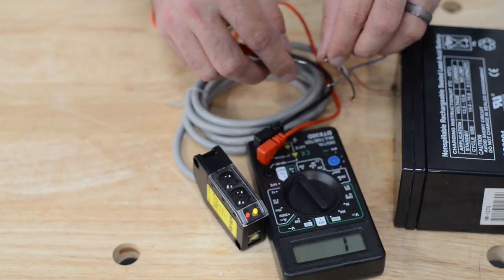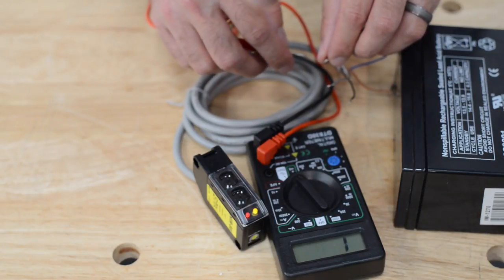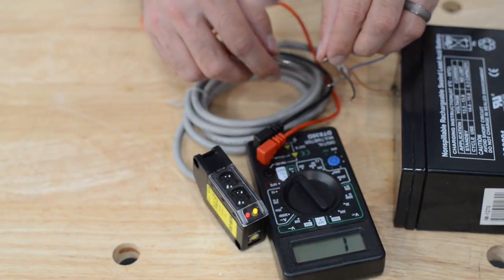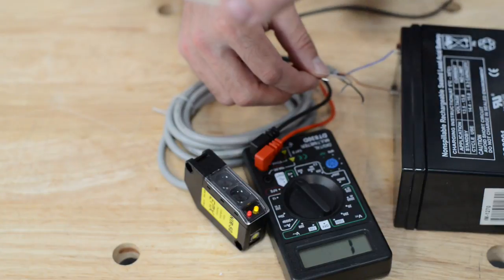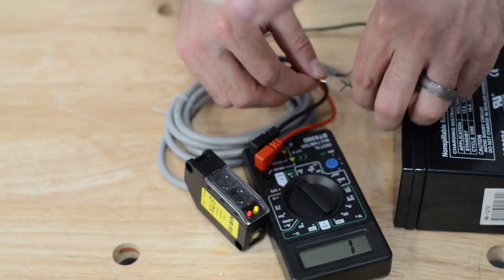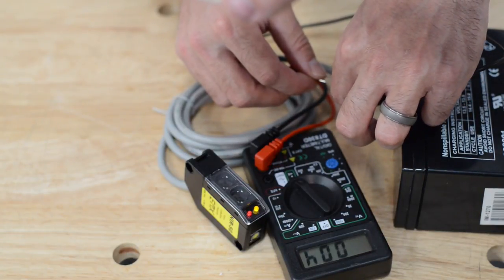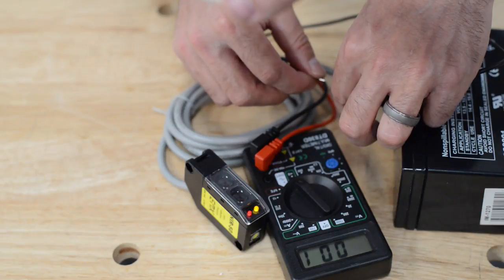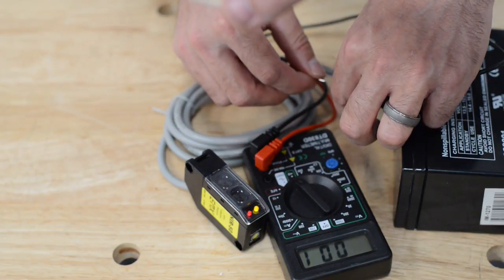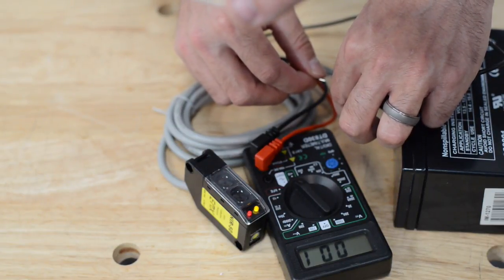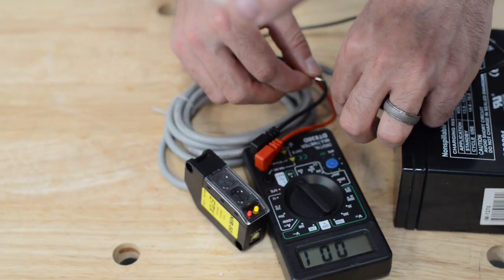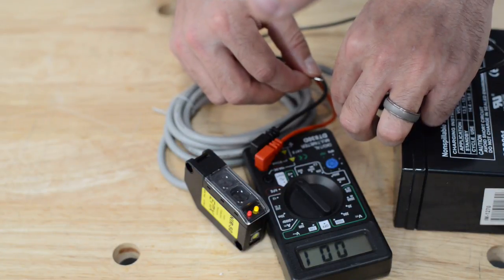So one of these two wires is common and one of these two wires is normally open. Leaving one on the white, I'm going to put the other lead on the black. So I have continuity. So now I know because I knew one of the white or the gray was the common. Again, I knew the black had to be my normally closed.